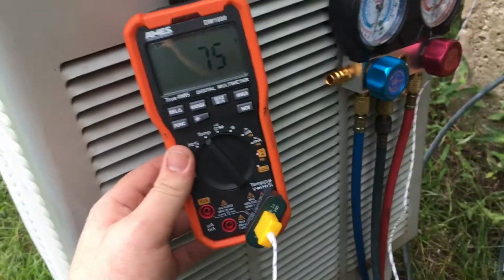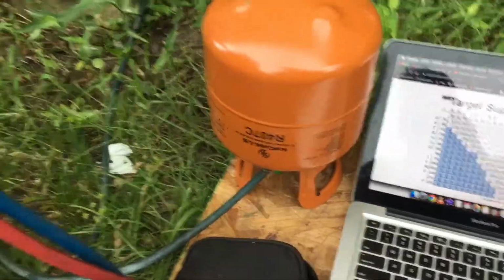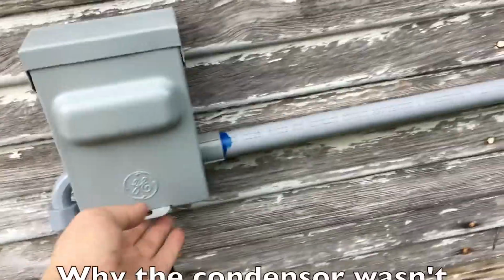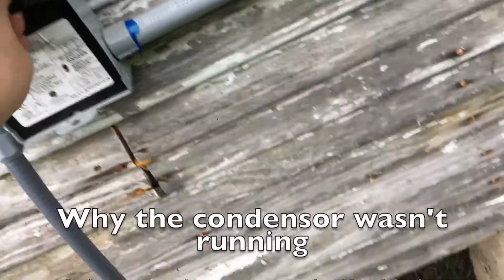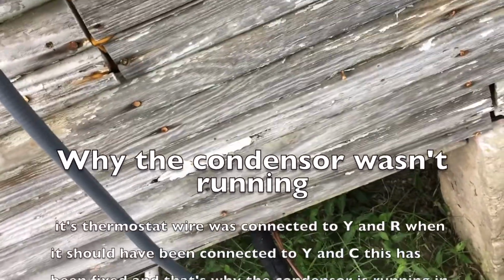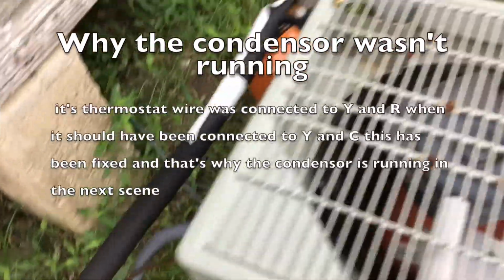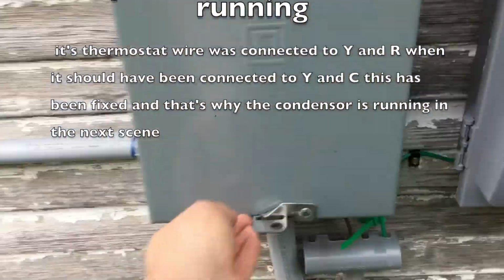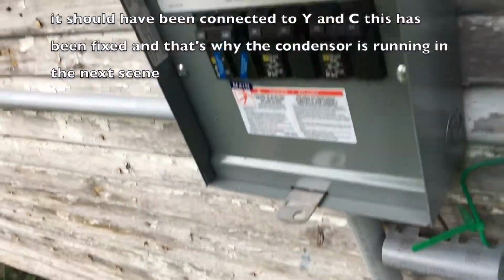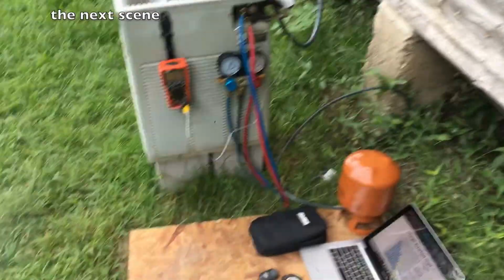Okay, we're finally ready to start charging. I got everything set up here. I got my multimeter with thermocouple taped to the suction line for taking superheat. Got my target superheat chart, refrigerant already purged the line and everything. All I got to do is start this unit running. I've already got it turned on inside. Just need to plug in the disconnect. Well, disconnect was already plugged in. Breaker's on. Alright, let me go see what's wrong inside.